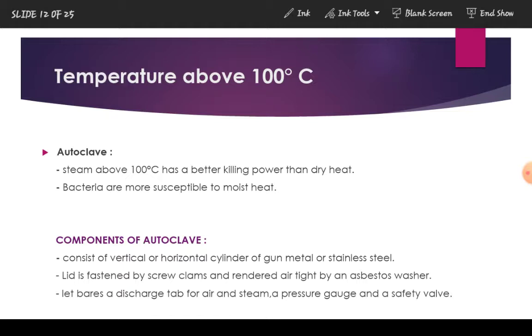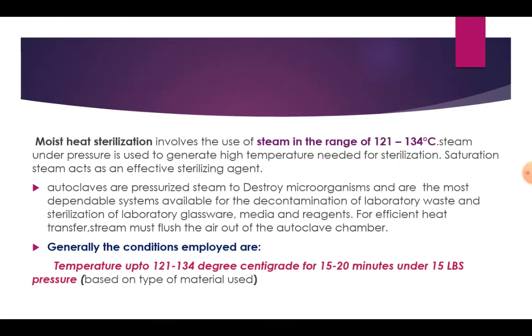Lid is fastened by screw clamps and rendered airtight by an asbestos washer. Lid bears a discharge tap for air and steam, a pressure gauge, and a safety valve. Moist heat sterilization involves the use of steam in the range of 121 degrees Celsius to 134 degrees Celsius. Steam under pressure is used to generate the high temperature needed for sterilization. Saturated steam acts as an effective sterilizing agent.